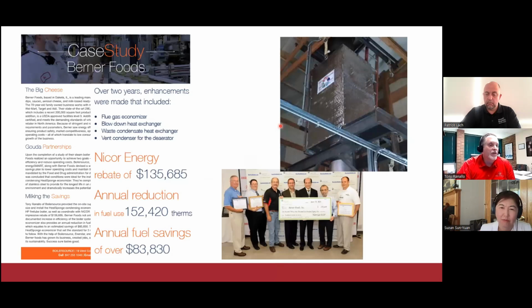This is a case study. This is one of our earlier ones where we were able to proof of concept here. This is actually a customer that was looking to purchase a new boiler, and they decided to look at heat recovery instead. That's like a two-stage condensing economizer up there on top of a boiler, and they were able to reduce their fuel usage by 152,000 therms a year. They got a rebate from the gas company Nicor for about $136,000. And they reduced annual fuel costs by about $83,000 back in the day. So it was a nice case study, and they actually duplicated it. They did lather, rinse, repeat 3 times or more on this particular facility.